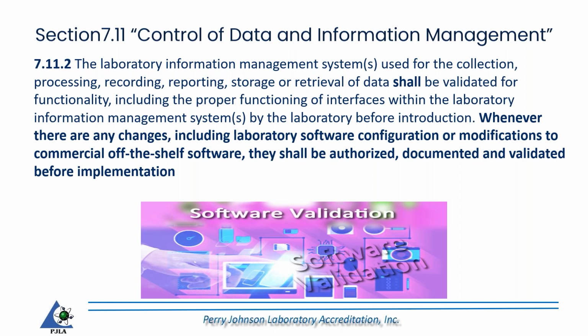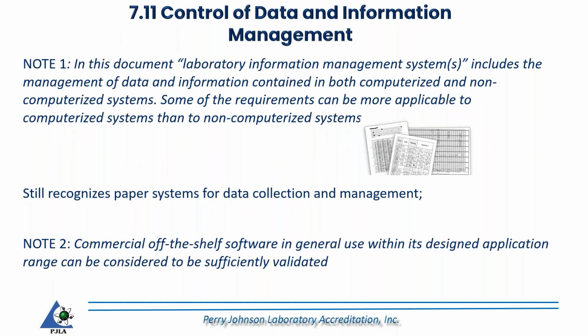So here we have a requirement that applies if you wrote your own software. Sometimes I hear Excel, for example. Excel itself does not need to be validated. However, if you're writing a spreadsheet yourself, particularly if it's looking up data or doing calculations, then you need to validate that. We have a couple of notes here. Again, this is right within the standard: the standard still recognizes paper systems, right there in the note.